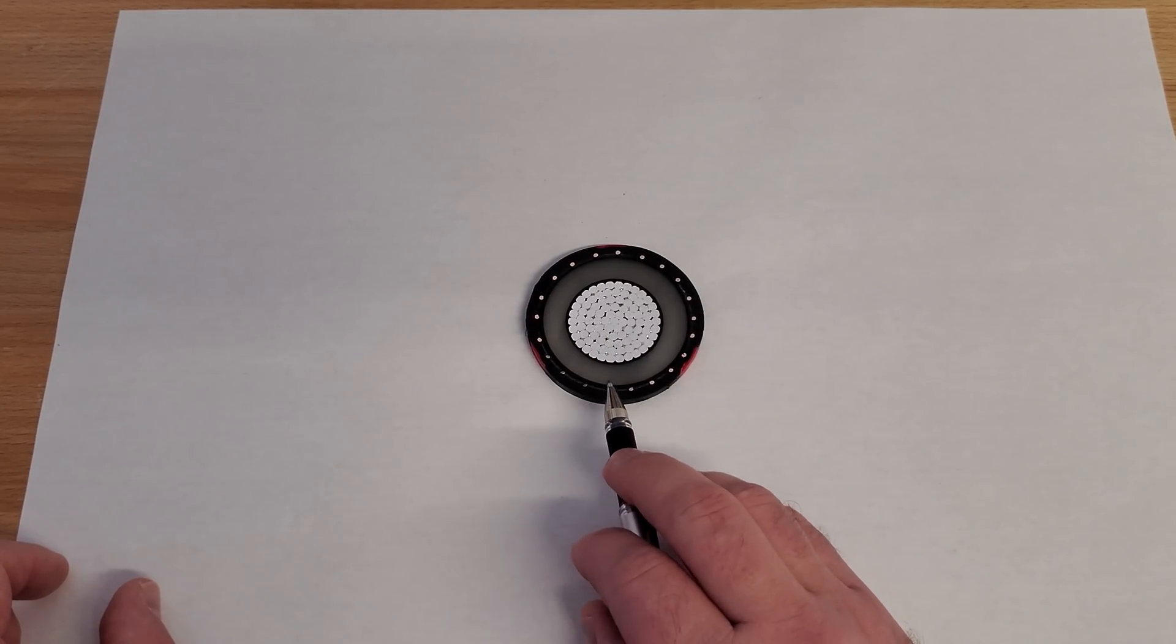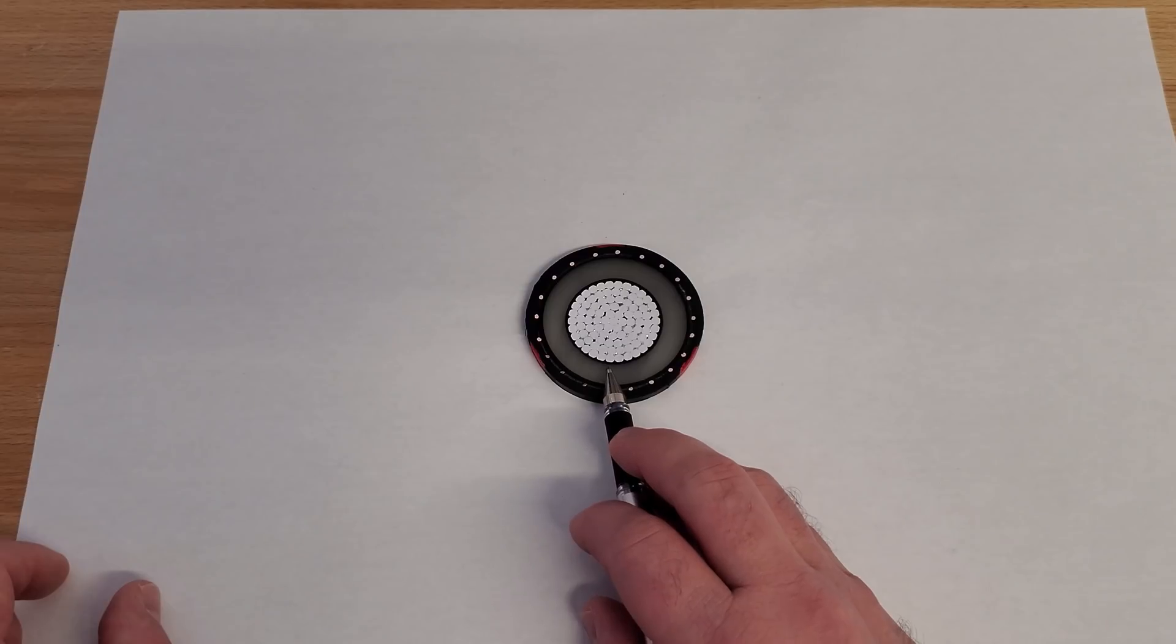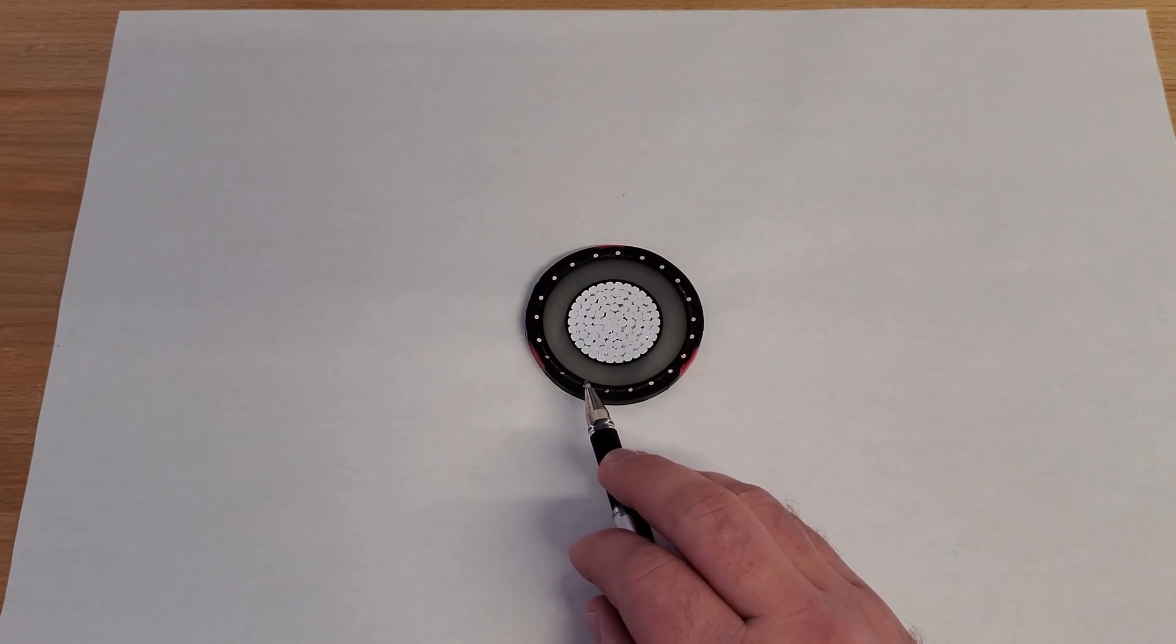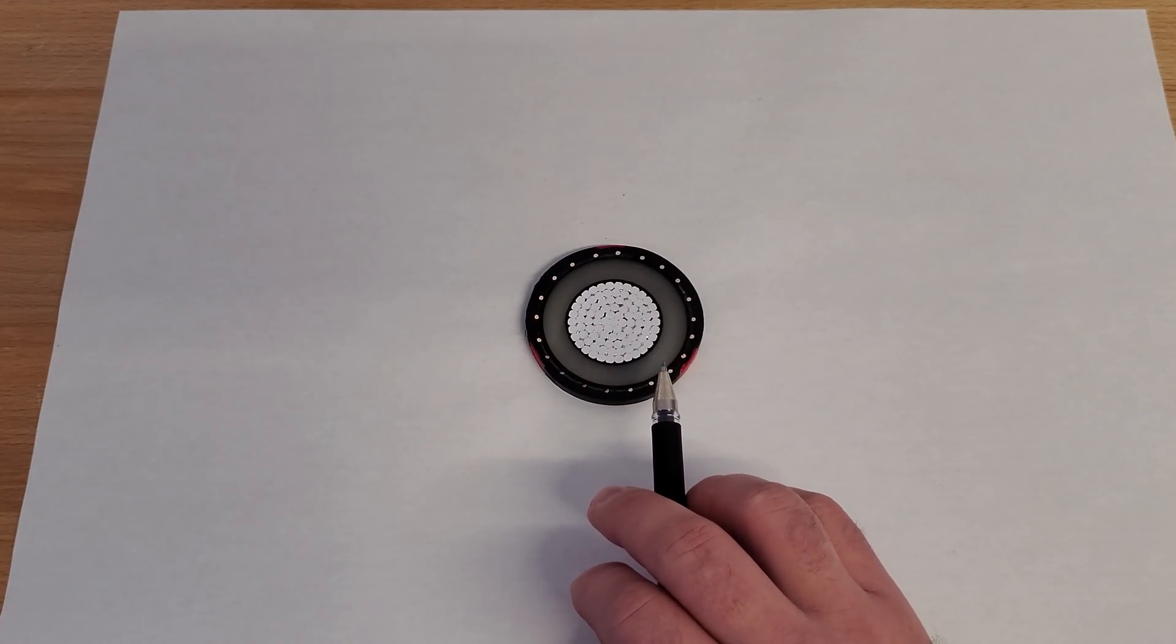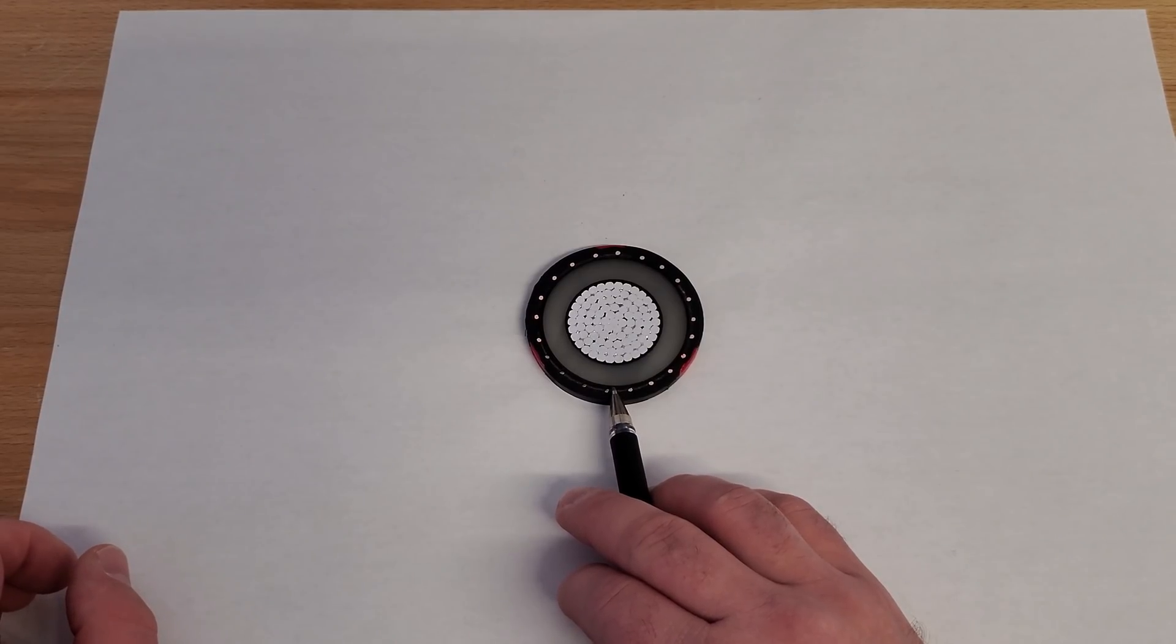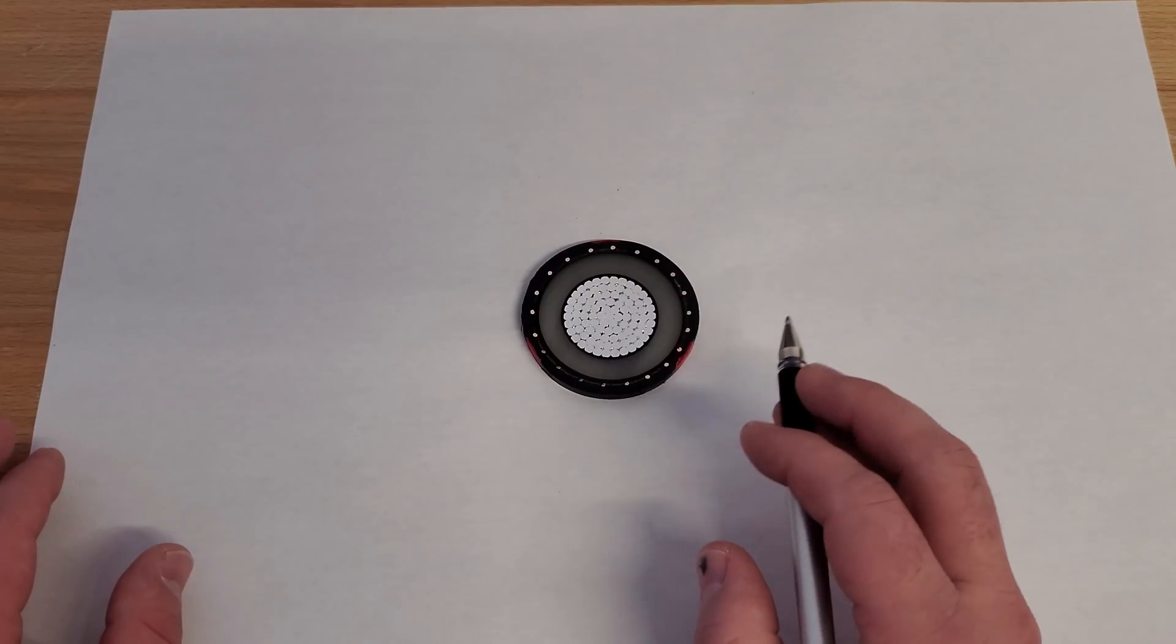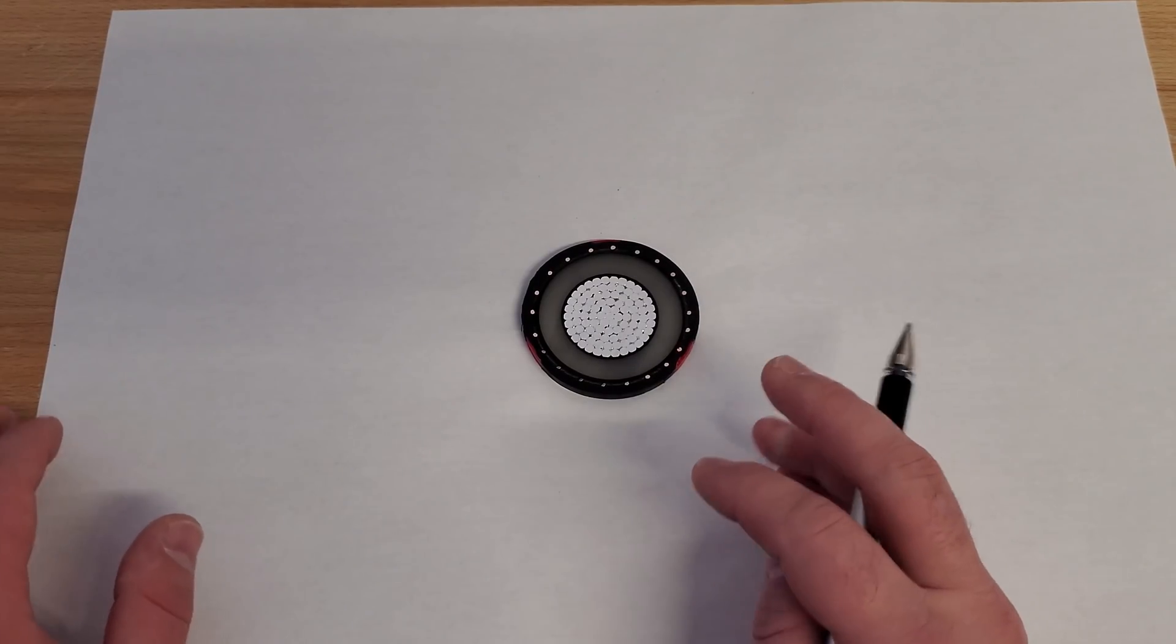So this one is the insulation shield. The other one is the conductor shield. We'll talk about the insulation shield next. That's actually the same material as the conductor shield. It is a semi-conductive layer. It's a polyethylene mixed with the acetylene black. That's what gives it the black color. And that's what allows it to be semi-conductive is because of that acetylene black conductive material impregnated into it. So why do we need the semi-con layer and that insulation shield?